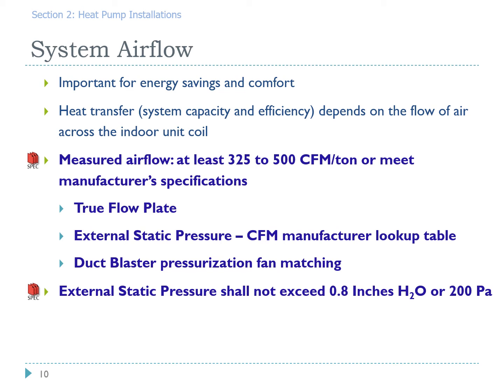Our specifications are needed to have measured airflow of at least 325 to 500 CFM per ton, or meet the manufacturer specification for non-variable speed systems. You must either test the airflow with a true flow measuring system, or identify the airflow using external static pressure CFM lookup tables from the manufacturer. If your manufacturer suggests a different airflow than the PTCS specifications, you can use that value, even if it's outside of the PTCS required 325 to 500 CFM per ton range. There's also an external static pressure of the duct system, and that external static pressure shall not exceed 0.8 inches of water column or 200 pascals.